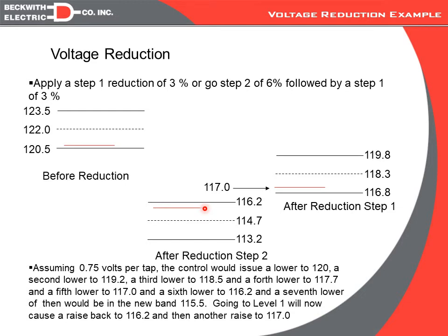Then if we do a level 1, a level 1 does 3% of the original band, which then would actually shift the band back up to 118.3. You can see now that we're actually starting out below the band and having to come up. And if we come up one tap, we will finish at 117, and that will be slightly above the 116.8, and we'll be back in band.